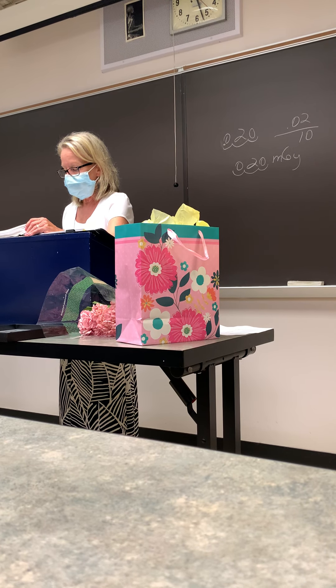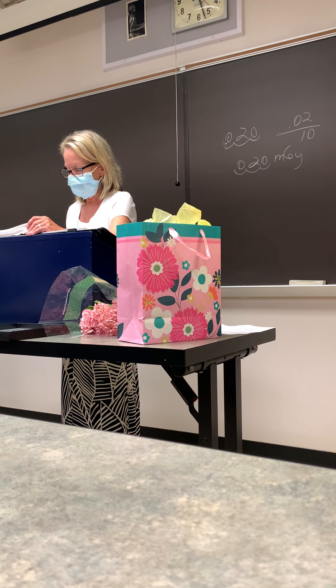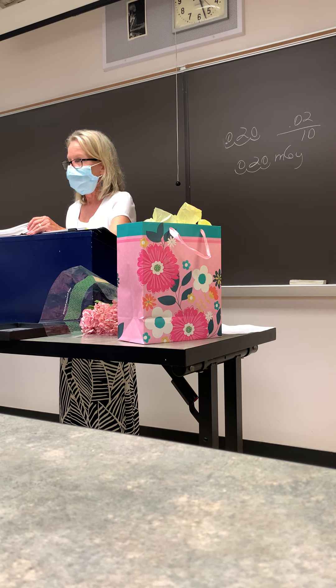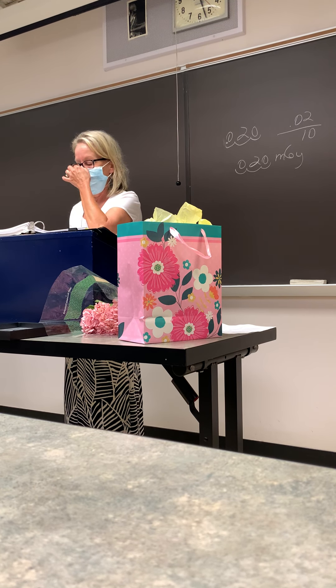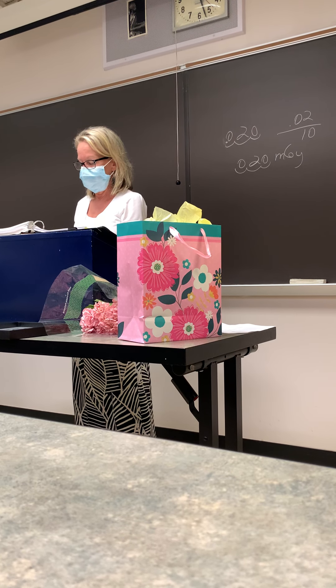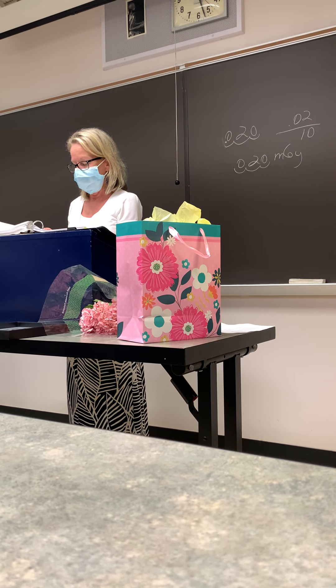Number eighty-nine: the tabletop exposure rate during fluoro shall not exceed B — 100 milligrays per minute.